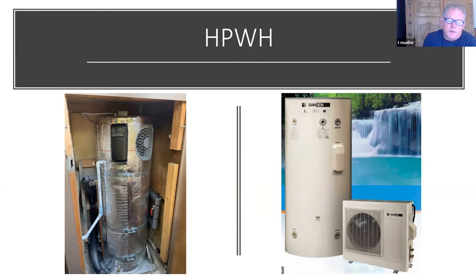There's usually a condensate line. That condensate is just distilled water, so it can go into a drain, unlike an instantaneous gas water heater that also has a condensate line you have to put out on the ground. The most challenging part of these is usually the electrical connection. Most of them are 240 volts, although there are now 120 volt models on the market also. So it usually requires some electrical work, which is one of the bigger installation expenses.